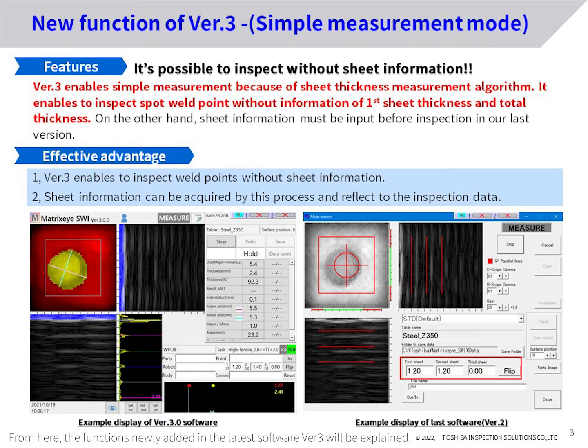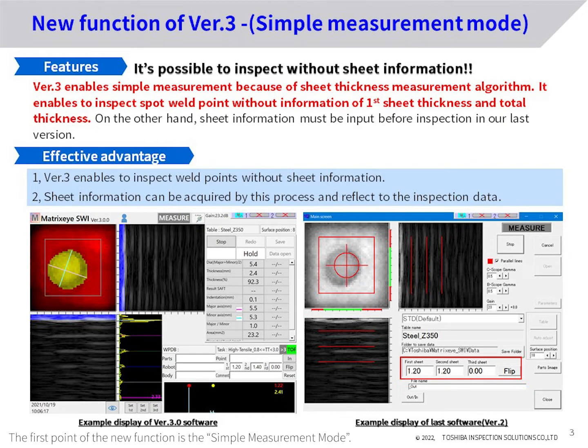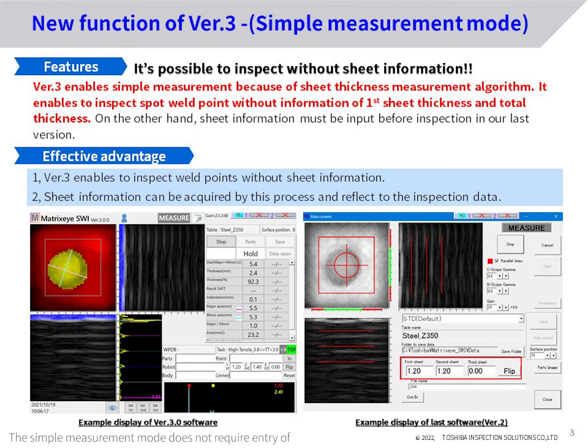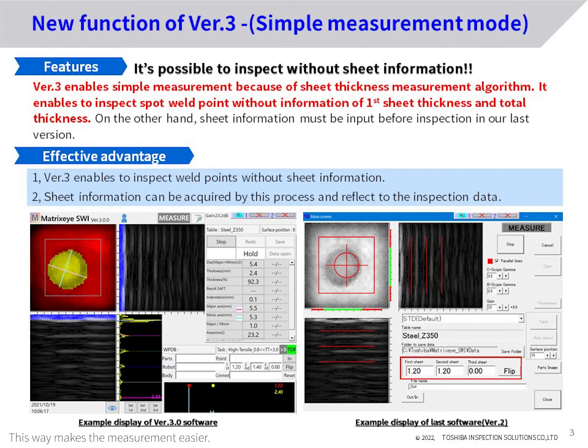From here, the functions newly added in the latest software version 3 will be explained. The first new function is the simple measurement mode. The simple measurement mode does not require entry of sheet thickness information in advance, making the measurement easier. This makes it possible to cope with sudden inspections at your shop or production lines when there is no sheet thickness information available.